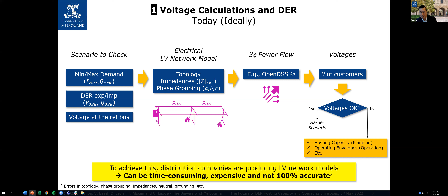Actually, it's fantastic. However, it can be extremely time consuming and expensive if you want to get it right, because you need to send people sometimes to check. And unfortunately, even if you do that, it will not be 100% accurate. There are always some errors in topologies, errors in phase groupings, errors in impedances. The neutral is very difficult to tell—how it's actually being used—or even the grounding, where exactly the neutral has been grounded. So it's very difficult to have it 100% accurate.